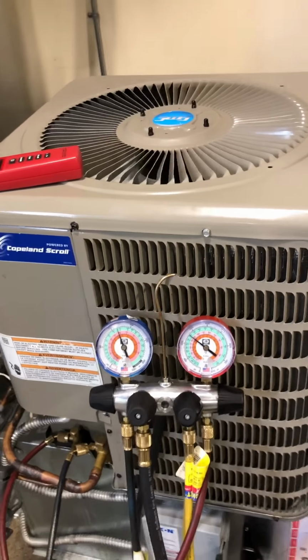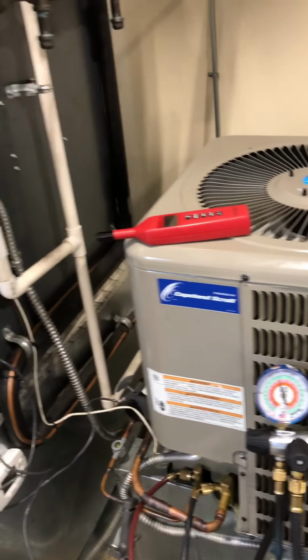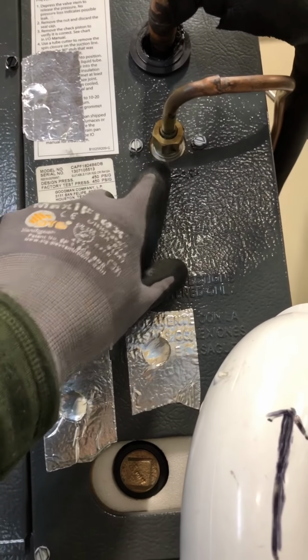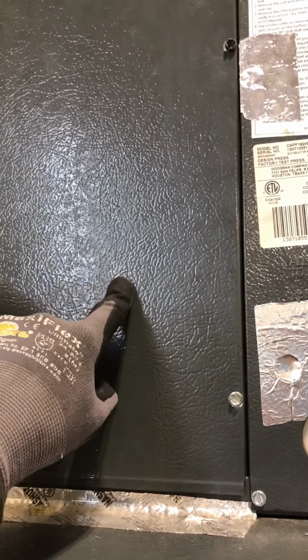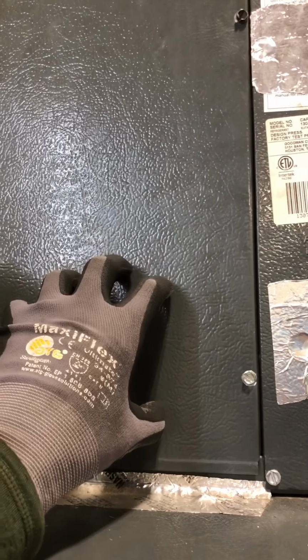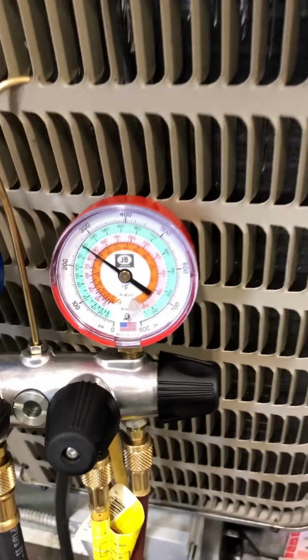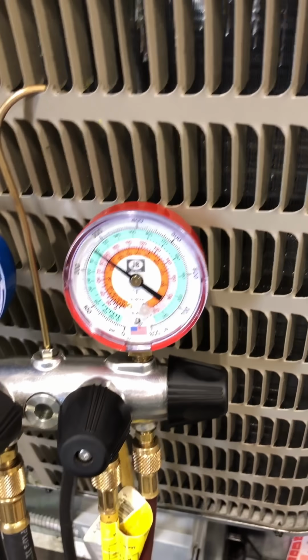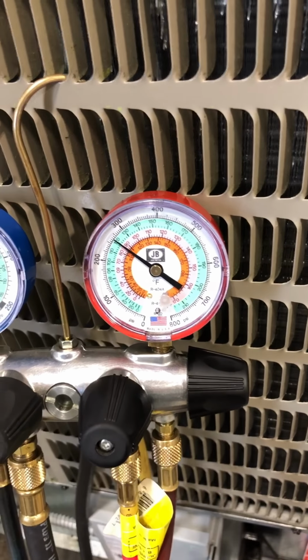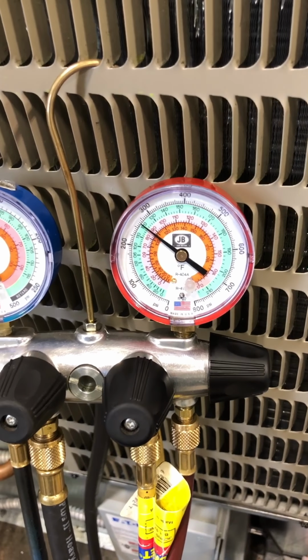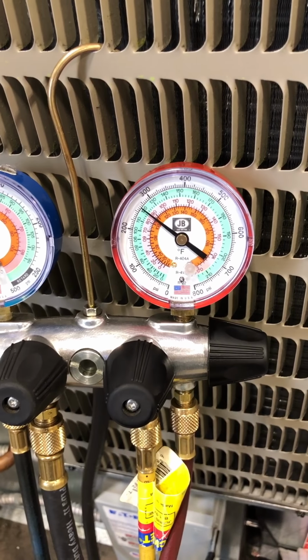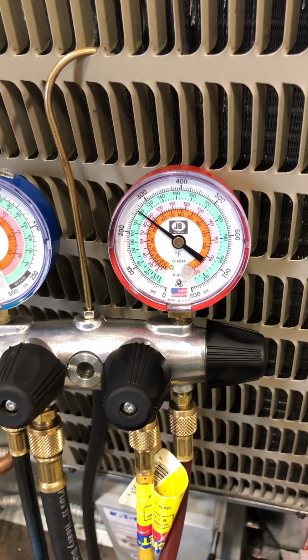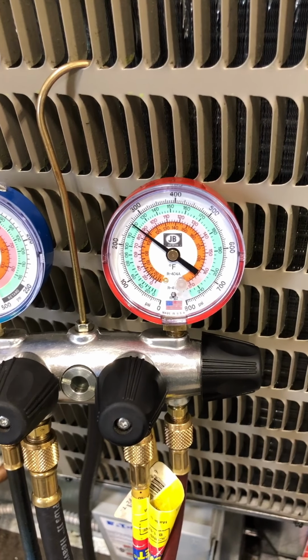The warmer our liquid is, the bigger difference there's going to be when we drop the pressure here, meaning we're going to lose more to flash gas, which means we're not going to hit this evaporator with as much liquid capacity as we should be. It's all a domino effect. So if I have a high condensing split, I probably have a dirty condensing coil. I'm just not getting enough air across it to cool that refrigerant down as much as I should be. I gotta check that condensing split.